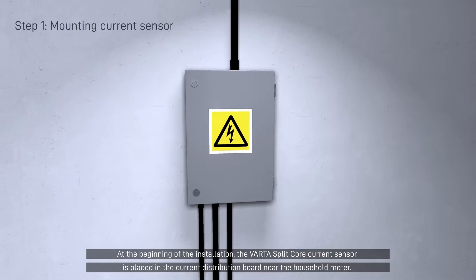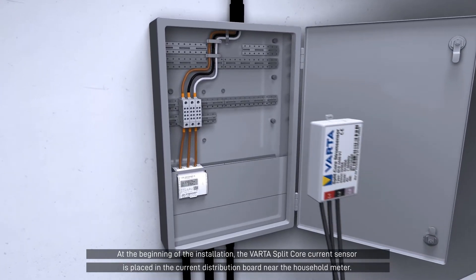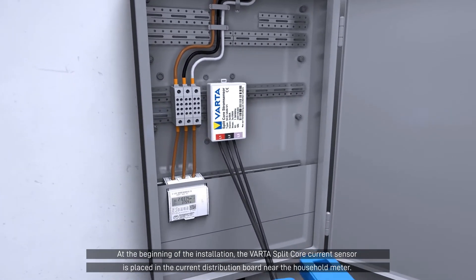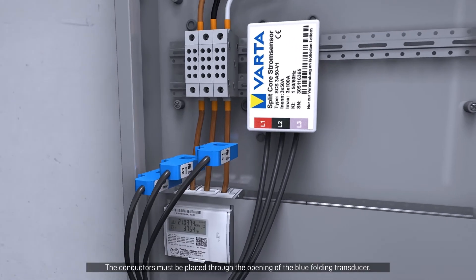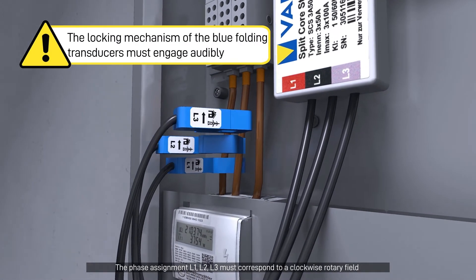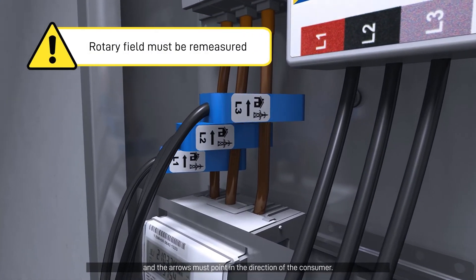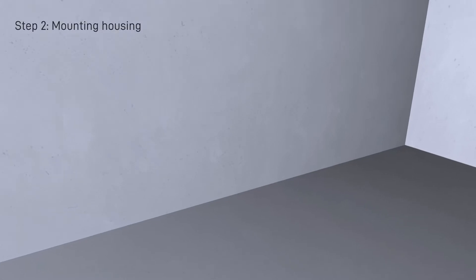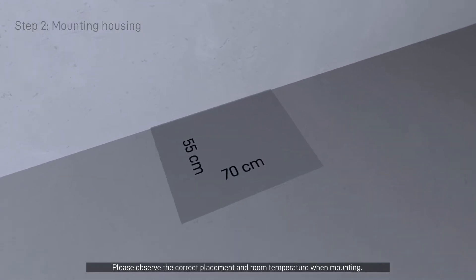At the beginning of the installation, the VARTA Split Core Current Sensor is placed in the current distribution board near the household meter. The conductors must be placed through the opening of the blue folding transducer. The phase assignment L1, L2, L3 must correspond to a clockwise rotary field and the arrows must point in the direction of the consumer. Please observe the correct placement and room temperature when mounting.